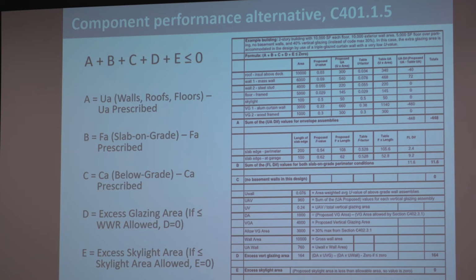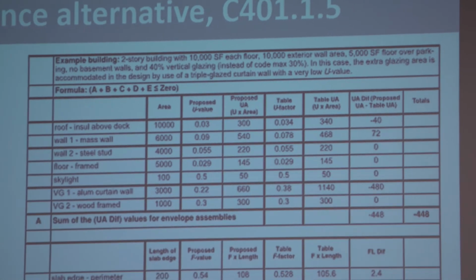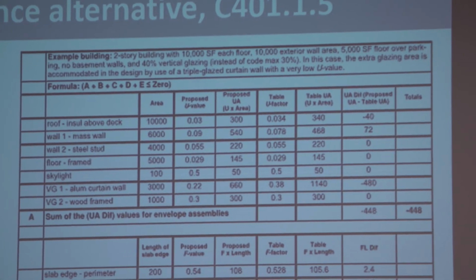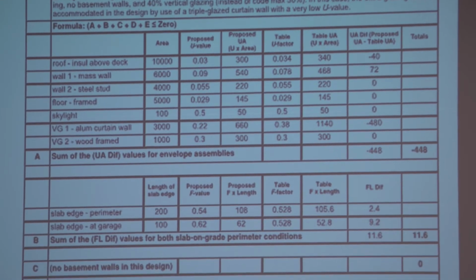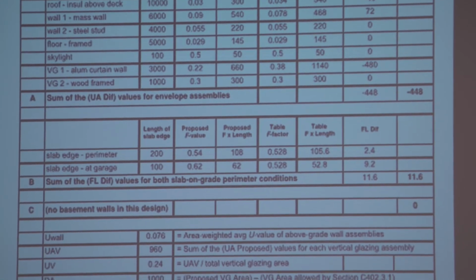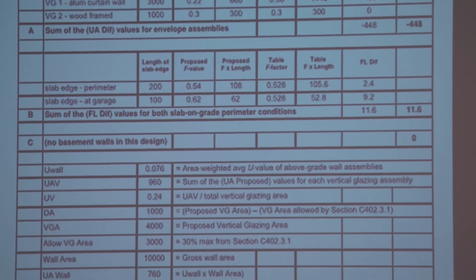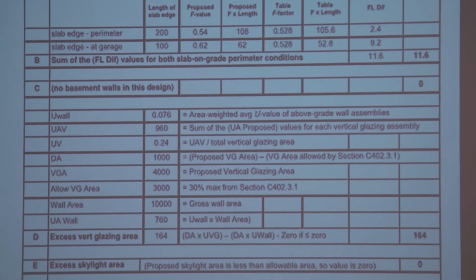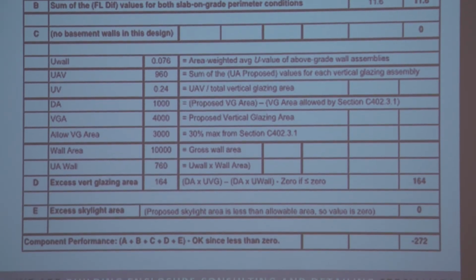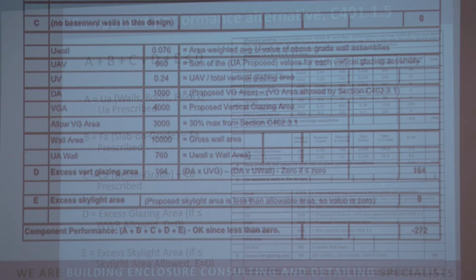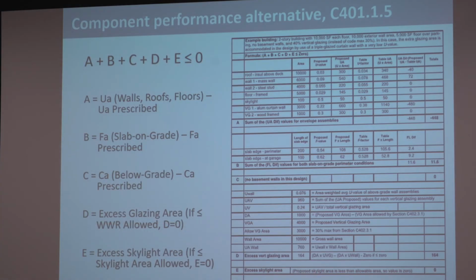Essentially what you're doing is you're adding up the U value of all your walls, roofs, and floors, your slab on grade and below grade, C and F factors. And then you're doing a calculation of essentially the excess glazing area. I want to increase my glazing area, so how much extra heat loss am I going to get in there? And they're essentially trying to quantify all of that, and how much potential excess skylight area. And so you can do these kinds of trade-offs using this spreadsheet and not necessarily going to a building energy model to be able to still be code compliant, but it potentially means adding a lot of wall and roof insulation to be able to accommodate slightly more glazing. So that's one method of compliance.